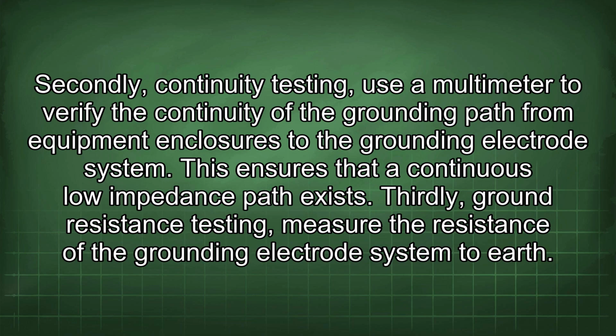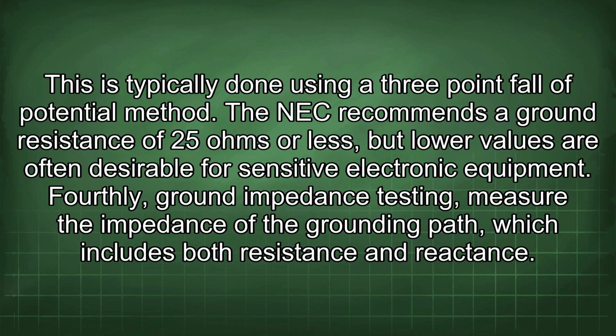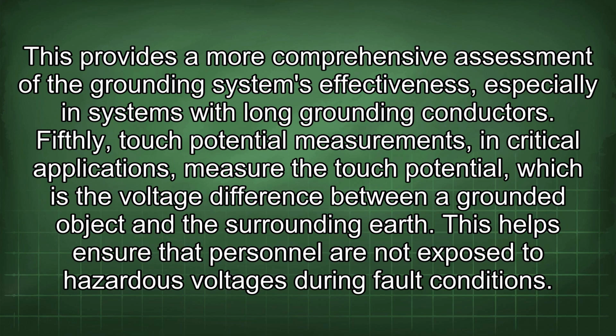Thirdly, ground resistance testing. Measure the resistance of the grounding electrode system to earth. This is typically done using a 3-point fall of potential method. The NEC recommends a ground resistance of 25 ohms or less, but lower values are often desirable for sensitive electronic equipment. Fourthly, ground impedance testing. Measure the impedance of the grounding path, which includes both resistance and reactance. This provides a more comprehensive assessment of the grounding system's effectiveness, especially in systems with long grounding conductors.